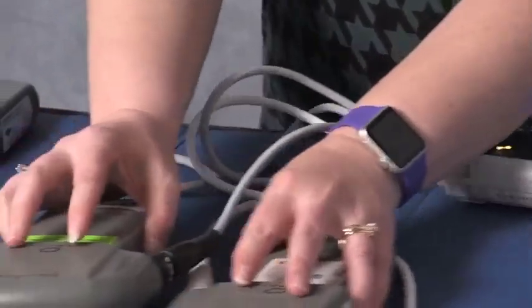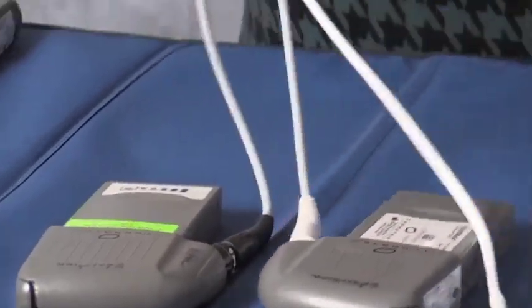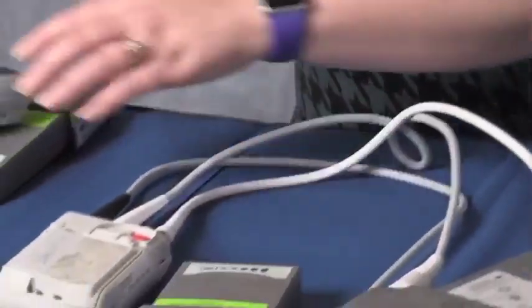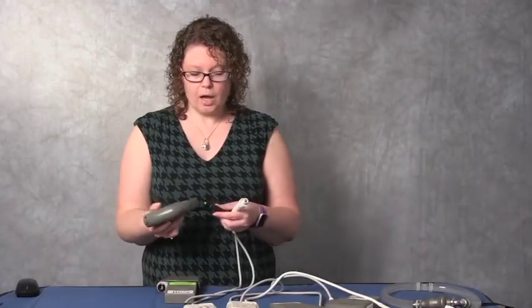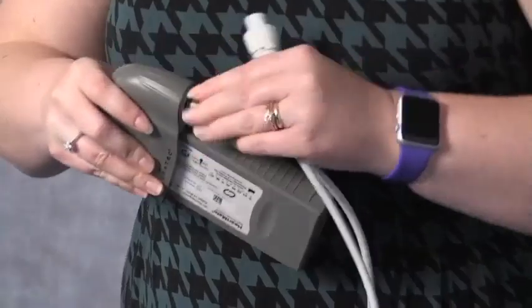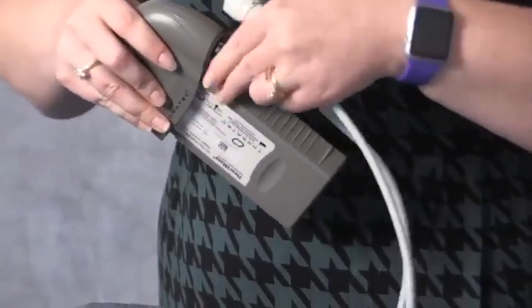Before we start unplugging anything, we want the patient to lay down or sit down so that if they do pass out when their pump is disconnected, they don't fall and hurt themselves. Once we've done that, I like to lay the controllers out right next to each other so that we're not fumbling for anything when we move that drive line over. And then finally, we need to plug the controller we're going to switch to into batteries so that the new controller has power connected to it.